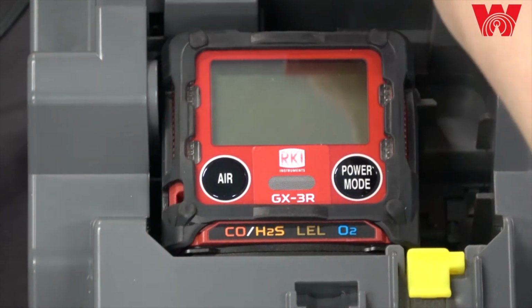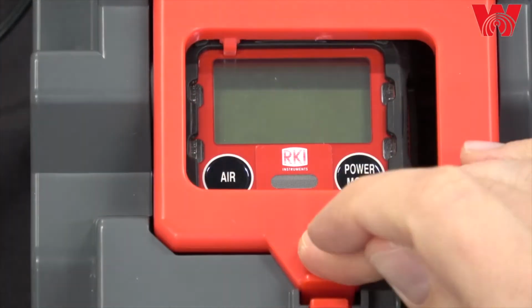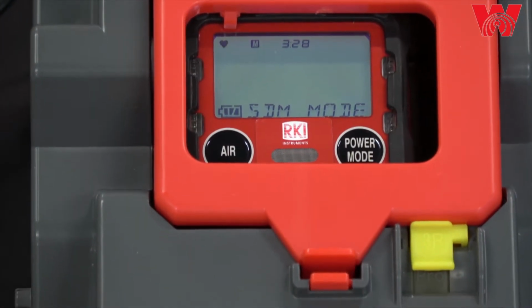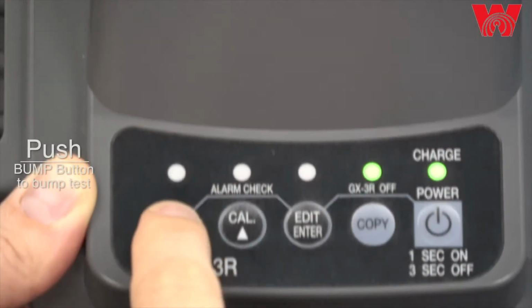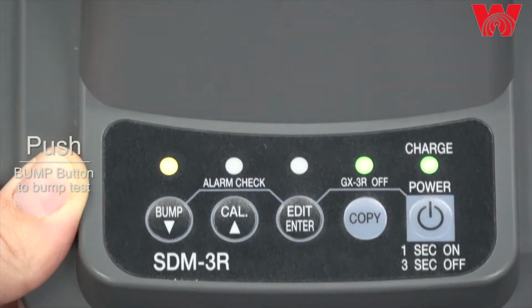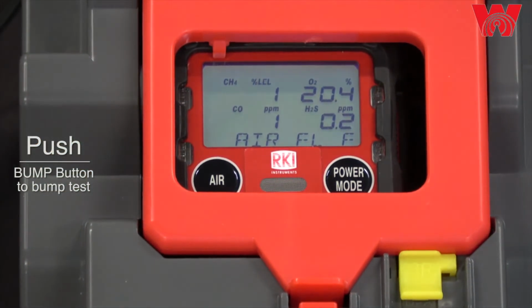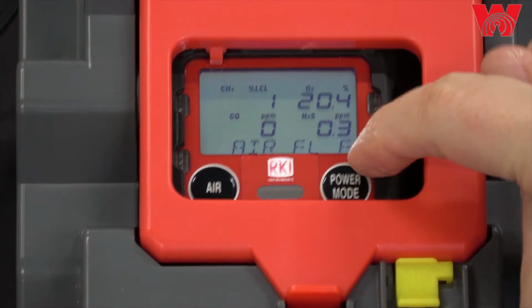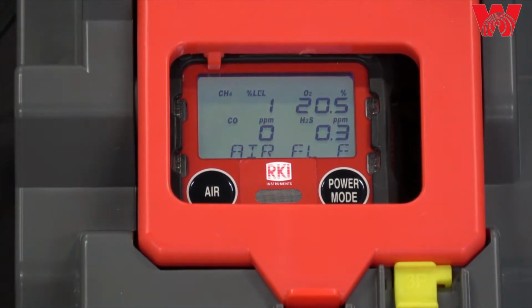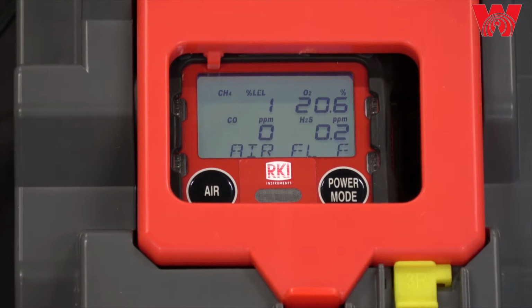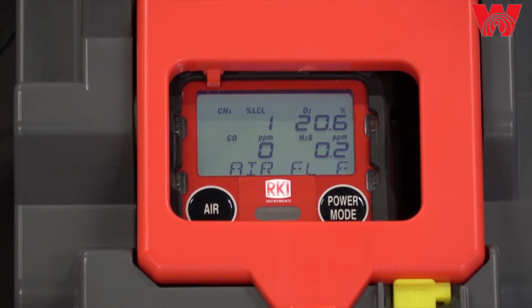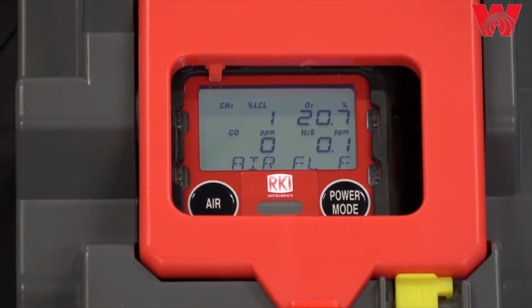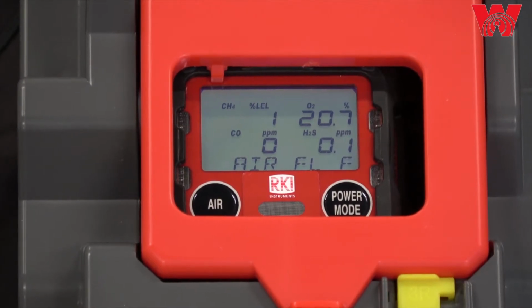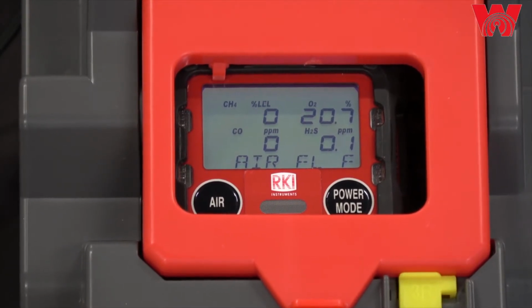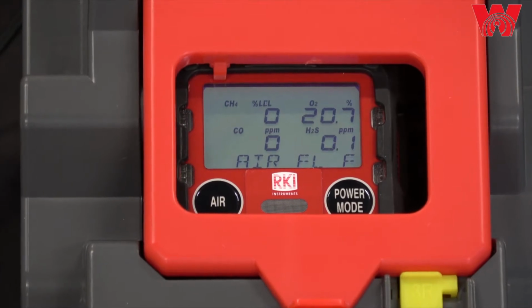So if you had just put your instrument in, you close the lid, and it turns on, press and hold bump. It's flushing with fresh air. You can see this F down here in the lower right corner. That means the docking station is going to do a fast bump. It's going to apply calibration gas, and then it's going to let it sit there, and it's going to take the highest LEL, CO, and H2S reading and the lowest oxygen.